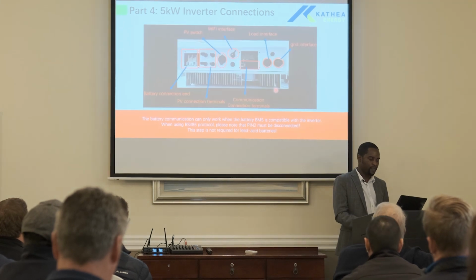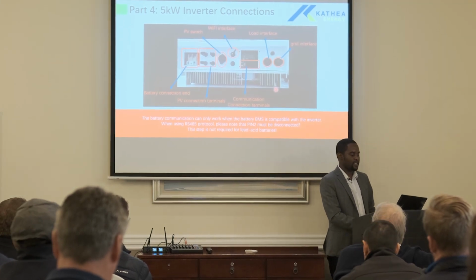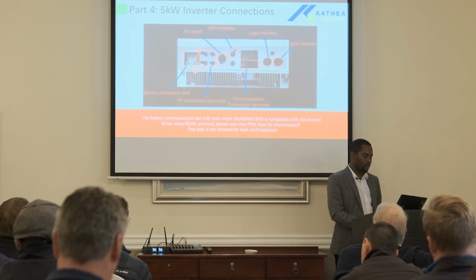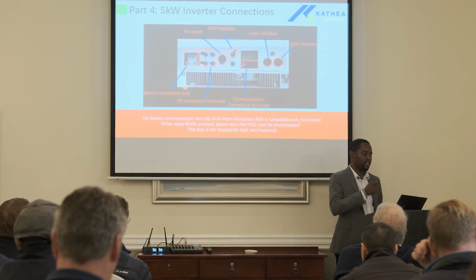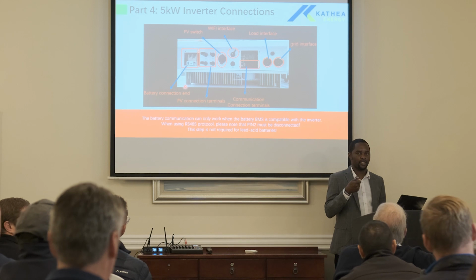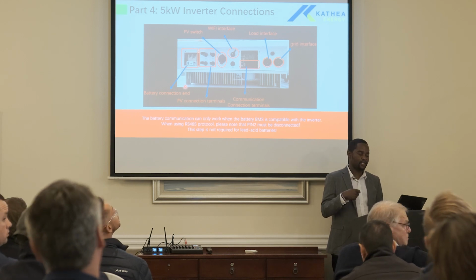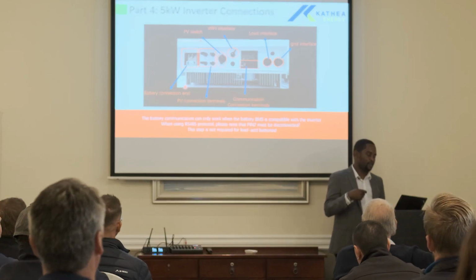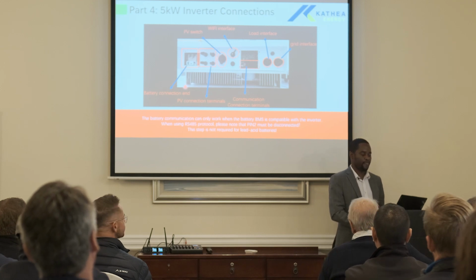Then you've got a gen port, still with the same connection. It's just press and release, then it's tight enough. Then on the 5 kilowatt, it's a bit different on the bottom. You can see that this is a battery termination. You actually unscrew it and you plug it out. You wire it from the outside, then you plug it in again.